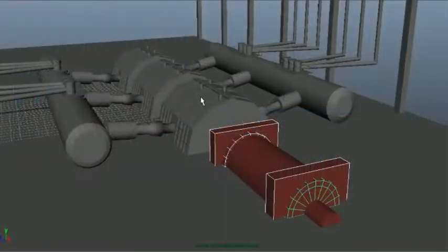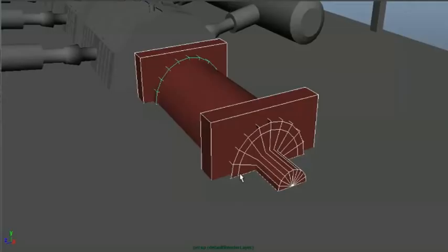So the generators which run through steam turbines usually have longer length and small diameter because they run at higher speed. Whereas the generators which run on water turbines can have big diameter and short length as they run at lower speed. As we have discussed, they run in the speed range of 1500 RPM to 3600 RPM. So they cannot be made for big diameter, otherwise their rotor will get damaged due to centrifugal force.